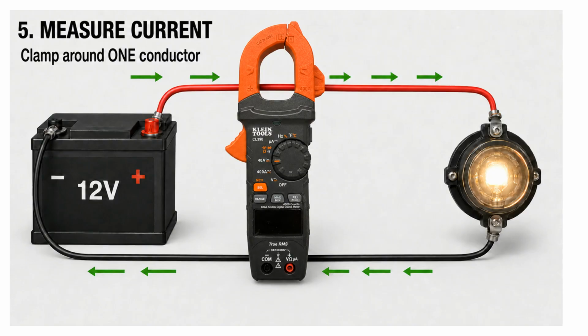The test leads are not needed for this measurement. Open the clamp and place only the red positive wire through the center opening. Close the clamp completely. The red wire must pass through the clamp. The clamp cannot simply lie on top of the wire. The black negative wire stays outside the clamp.